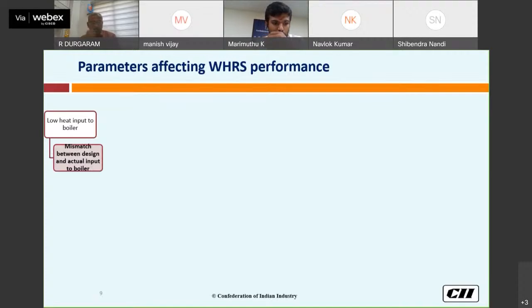For the low heat input to the boiler, based on our study, what we conclude is the first one is a mismatch between design and actual heat input to the boiler. Mismatch means that at the design stage, the waste heat coming from the cooler or preheater which we consider is not matching with the actual. So that gets reduced with the generation.